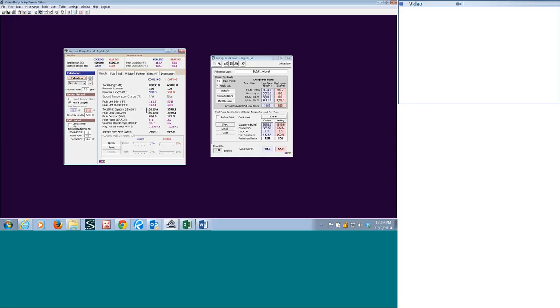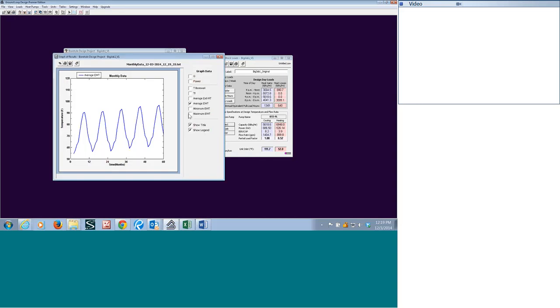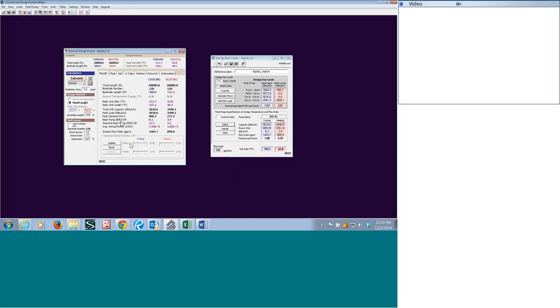Wow, what a difference. Since this job had overheated the first year, this is not much of a surprise. If we look at our temperature simulation projections, it's saying even in the first year, this loop should have been over 100 degrees. So that's telling us that, yeah, we may have an undersized loop here. So if we've determined that the original loads were insufficient for whatever reason, and we actually have more heat to reject to this loop field.